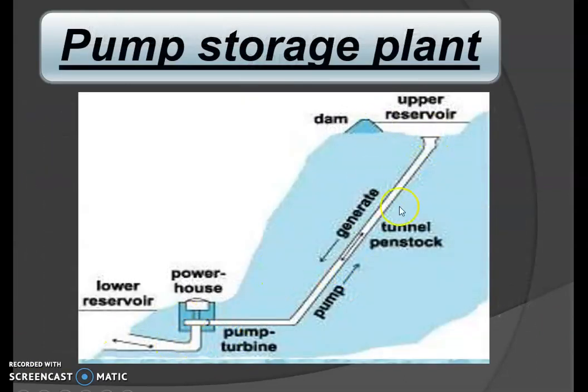Like this is the figure. When there is the rainy season, generally the upper reservoir is filled completely with water and the hydro plant can be used as such. But in the drought season, when there is not enough water available in the upper reservoir, the water is pumped back from the lower reservoir, the tail race, to the upper reservoir for the normal working of the power plant. So there are two phases of working: the generation phase and the pumping phase. In the generation phase, generally turbines and generators work, whereas in the pumping phase, the pumps and motors work to pump the water back to the upper reservoir.